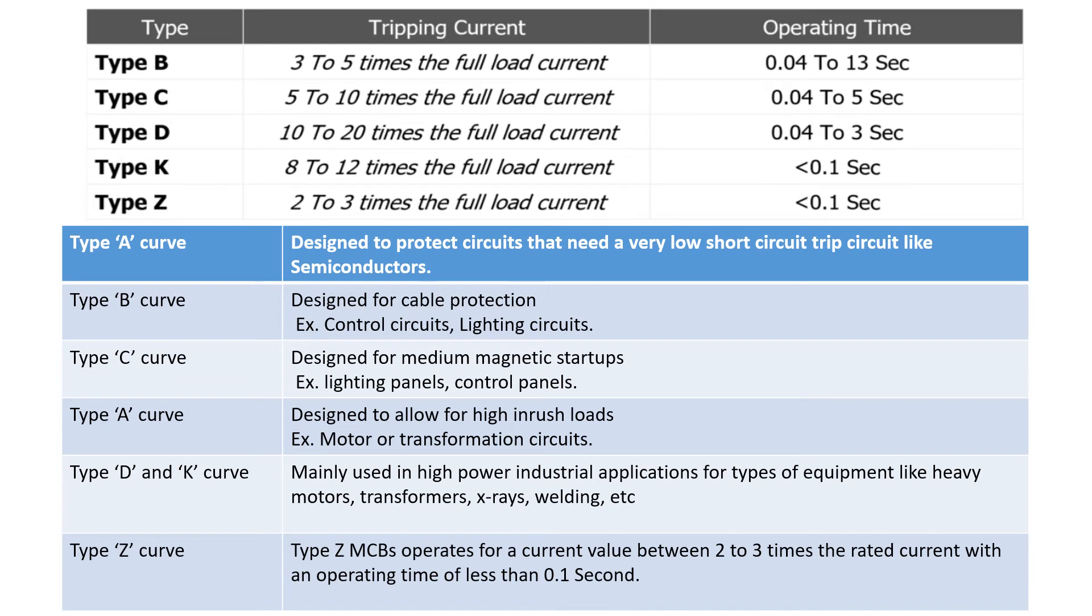This chart is for your reference which indicates you type of particular MCB and here its applications. So in fact there are type A, B, C, D, K and Z type MCBs with its tripping current and operating time. You can note down it from this particular slide and its application. Now class B type curve it is designed for cable protection for example control circuits and lighting circuits. So for domestic purpose we are preferring type B curve MCB.